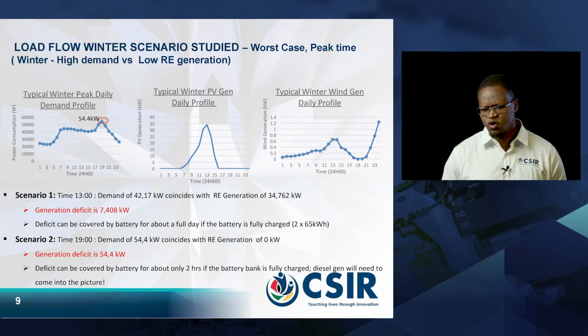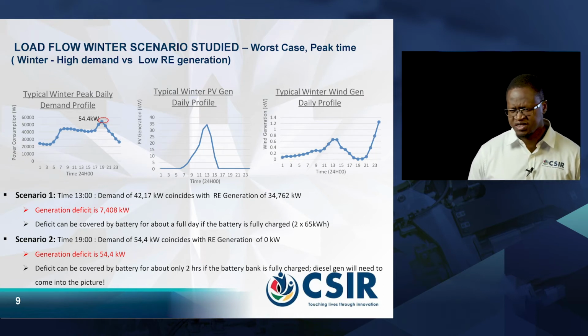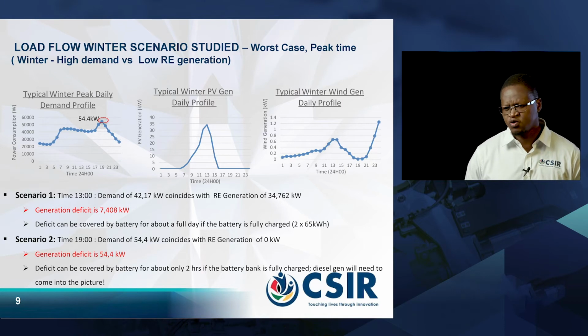In another scenario, later in the day around 1900, 7 o'clock in the evening, demand was around 54.4 kilowatts, coinciding with generation of 0 kilowatts, since there is no renewable energy generation at that time. This gives a deficit of 54.4 kilowatts, which can be catered for if the diesel generator is available and the battery bank is fully charged.